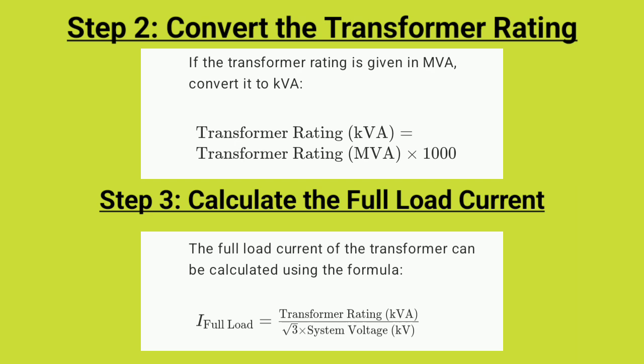Step 3. Calculate the full load current. The full load current of the transformer can be calculated using the formula: I_full load equals transformer rating in kVA divided by the square root of 3 times system voltage in kV. This gives the current under normal operating conditions.